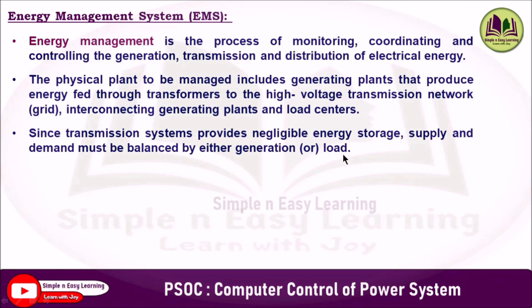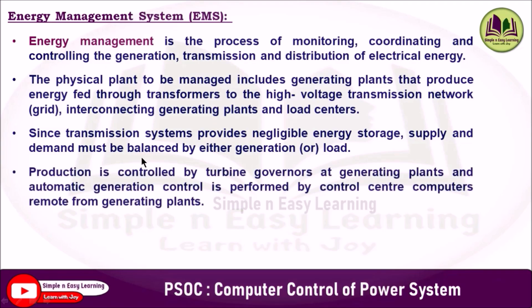Since negligible energy can be stored in the transmission system, we can obtain the power balance either by generation or load. The production is controlled by turbine governors at generating plants, and automatic generation control is performed by control center computers remote from generating plants, which is the energy control center.